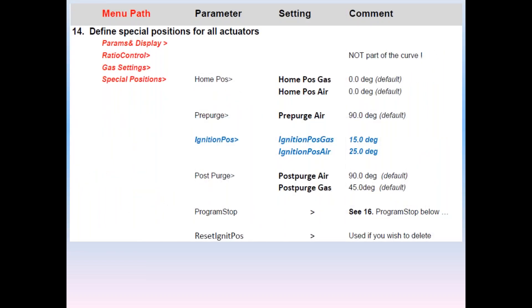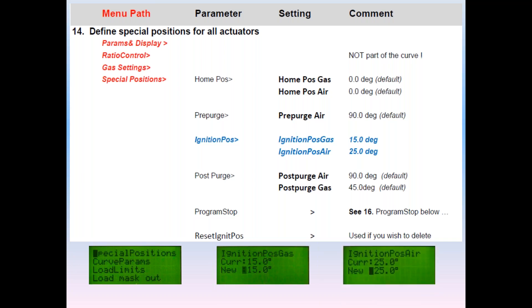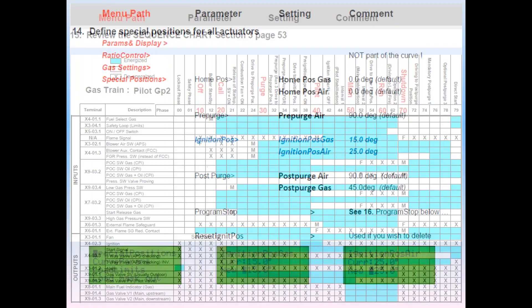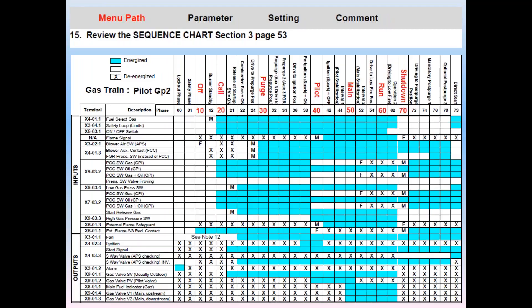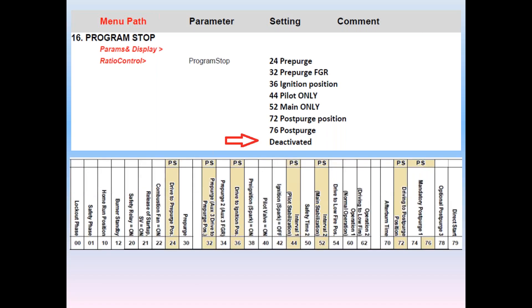Number 14. The LMV has no default settings for ignition positions. You must enter the values. In this example shown in blue are sample gas and air ignition position settings. This is what the AZL screen looks like for these settings. Go to special positions, ignition gas, ignition air. Number 15 is a quick overview of the sequence. Notice that the phase is advanced by the tens. And this details all the inputs and all the outputs for all the terminals based on the selected fuel train. Number 16. This feature is called program stop and similar to a run test physical switch found on some of the old flame safeguards. This allows us to hold the sequence at certain points. Note the PS program stop options in the sequence diagram. These are the phases where a sequence can be halted.